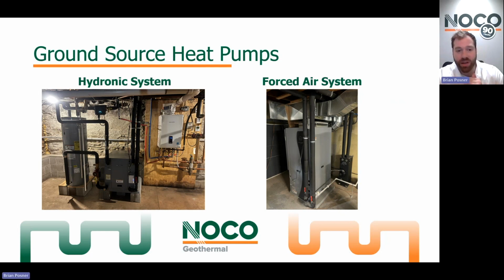Now on the left side of the screen is a hydronic system. If you have a boiler and hydronic heat, meaning radiant heat flooring, baseboard radiators, cast iron radiators, etc., you would get a hydronic heat pump. This would plug into your manifold in the exact same way your boiler previously did, and it would continue to heat your radiant flooring, your cast iron radiators, your baseboard radiators in whatever manner that your boiler previously did.